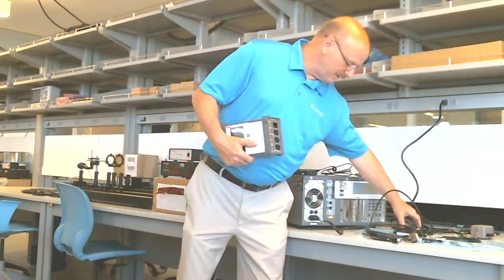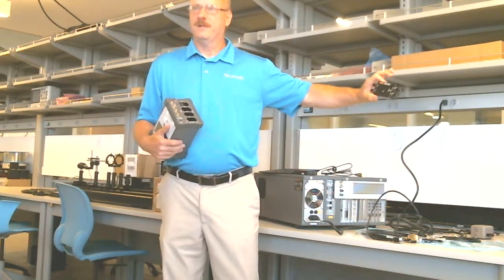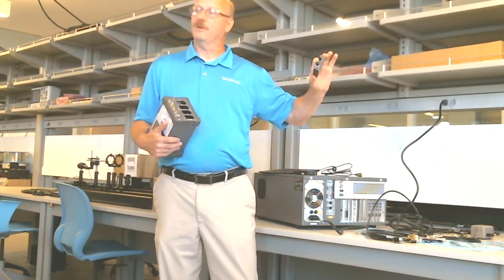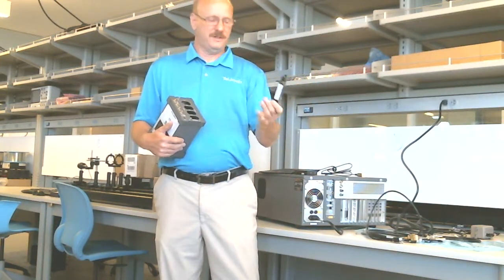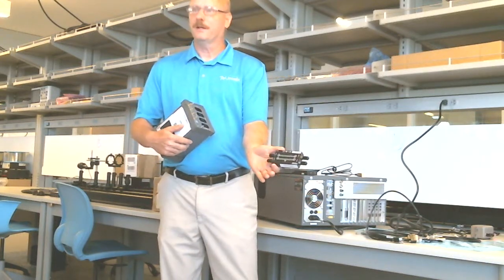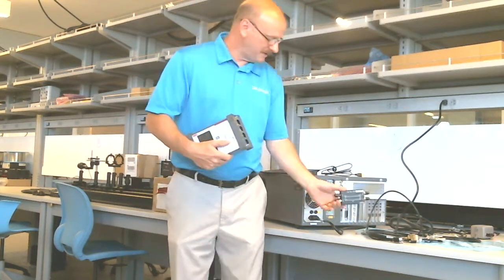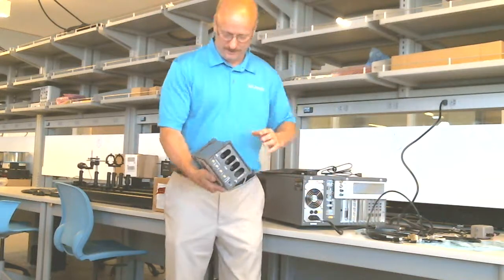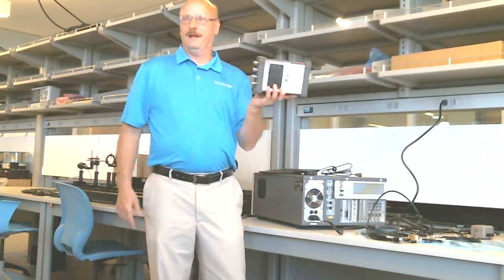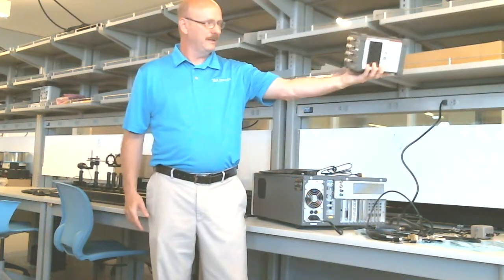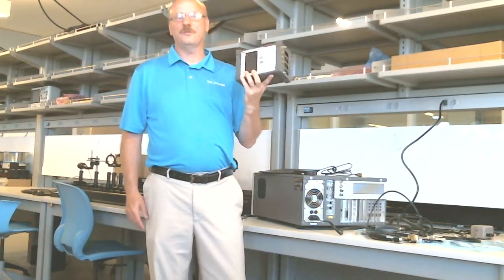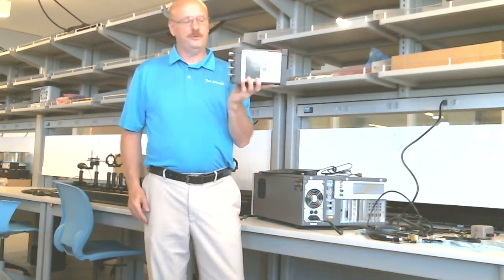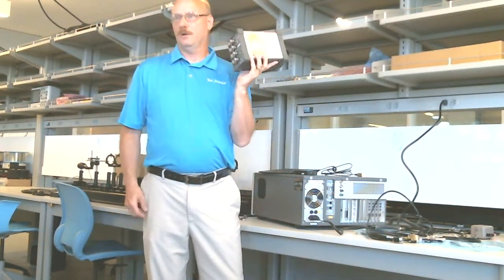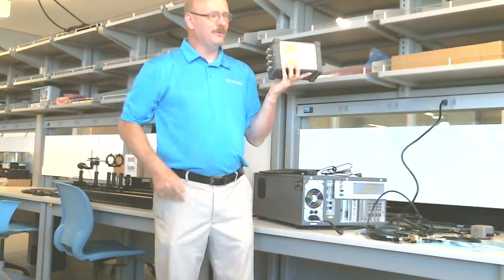Or they can accept these pass-throughs. Since you don't have preamps on all your channels, we use the pass-throughs. These are nothing more than a straight-through connection to bring your SMUs from the back of here to the front of here. Now guess where this goes? Right on your table, your probe station, as close to your probes as possible. Now you'll use 6-inch cables. Or actually you don't need any because you've got little short cables.